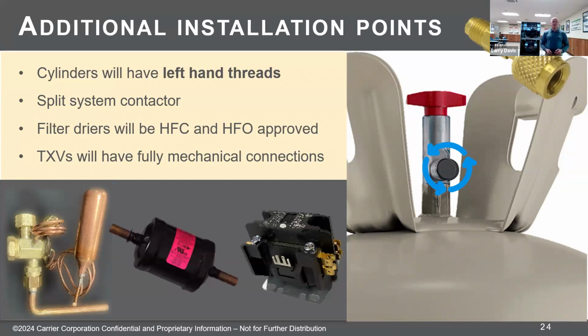The contactors in the outdoor unit are not a totally sealed contactor, but where before the top of the plunger for the contacts went through the cap of the contactor, that's going to be covered. And there'll be a little pinhole that you'll be able to use something small like an ink pen if you want to manually press a contactor. They're more enclosing the set of contacts where that arc takes place to reduce the risk of an arc flash. Okay. And we'll see some more on that when we talk about servicing these things a little later.